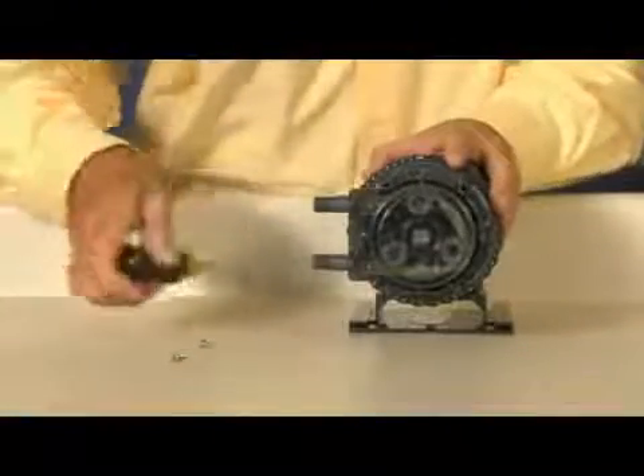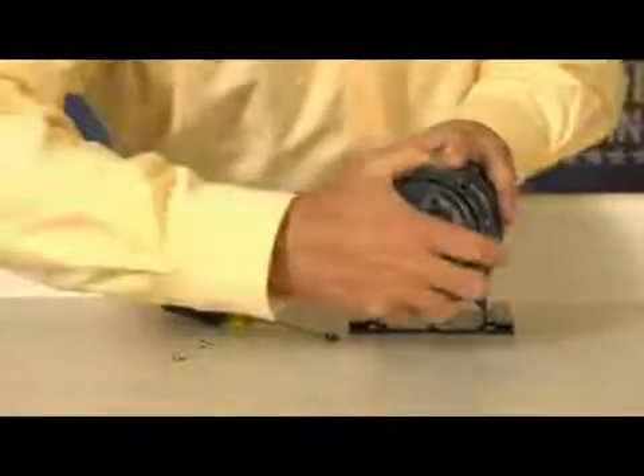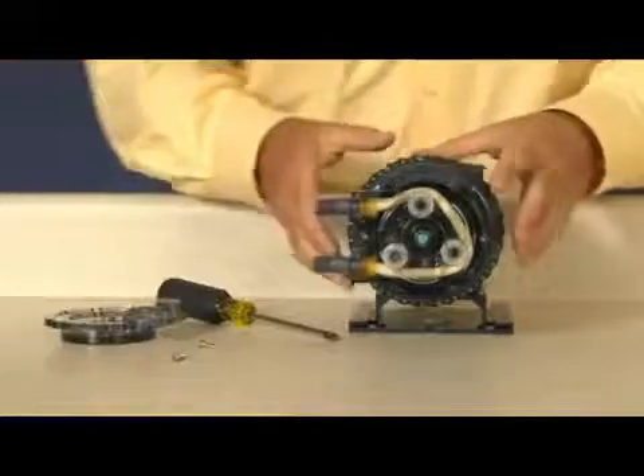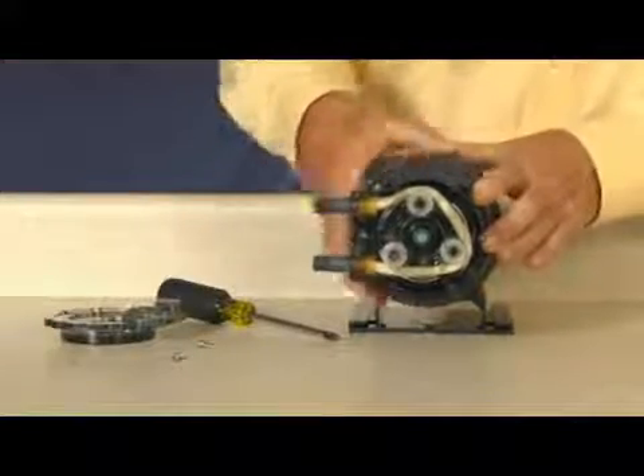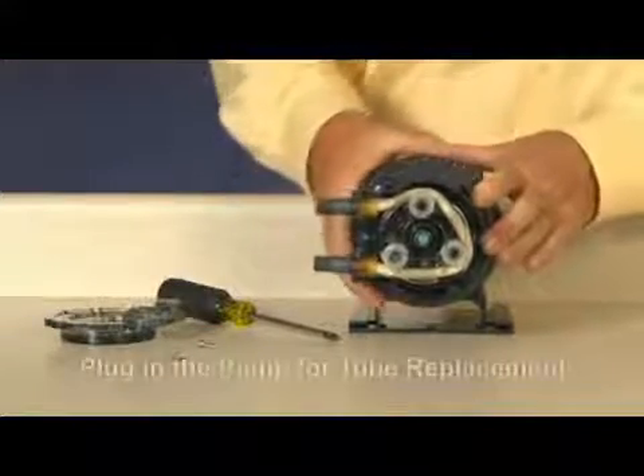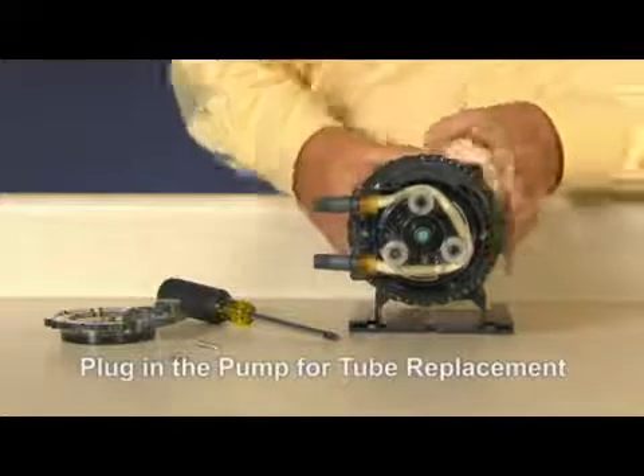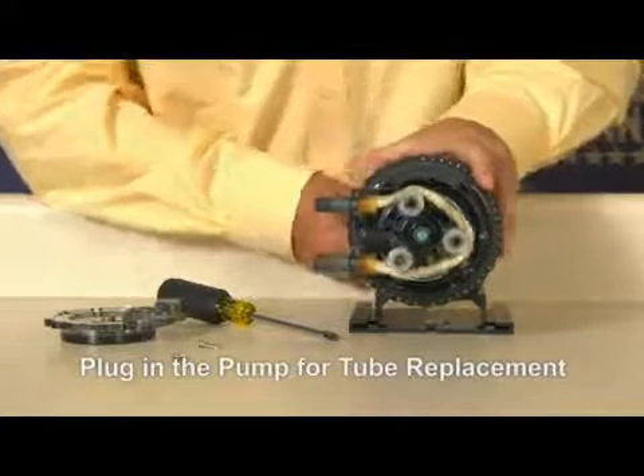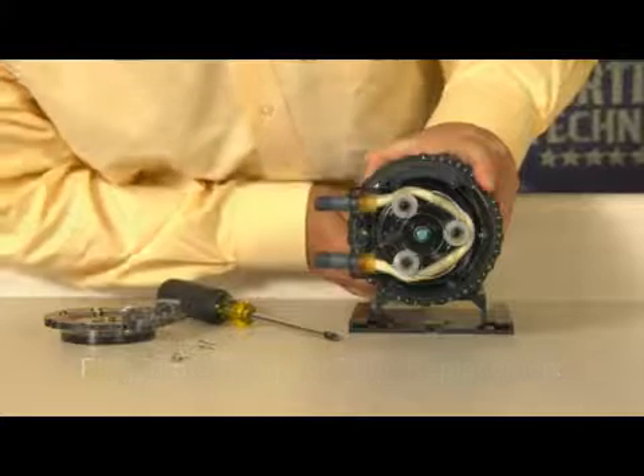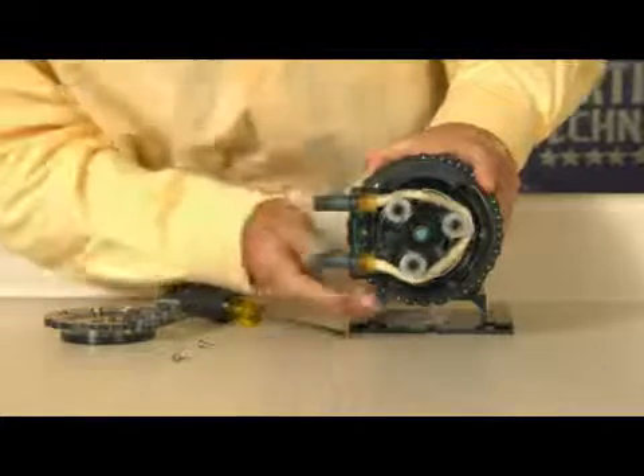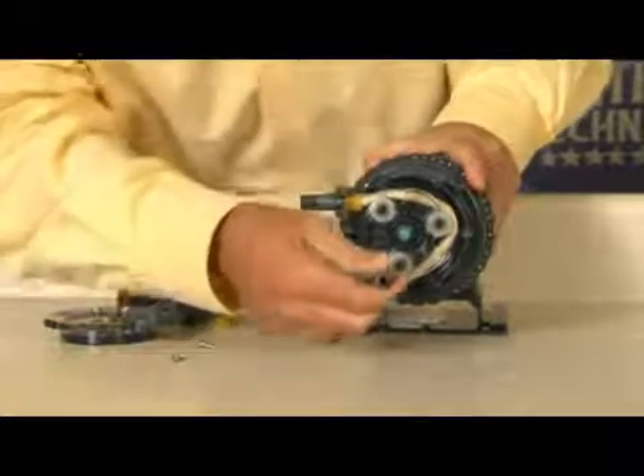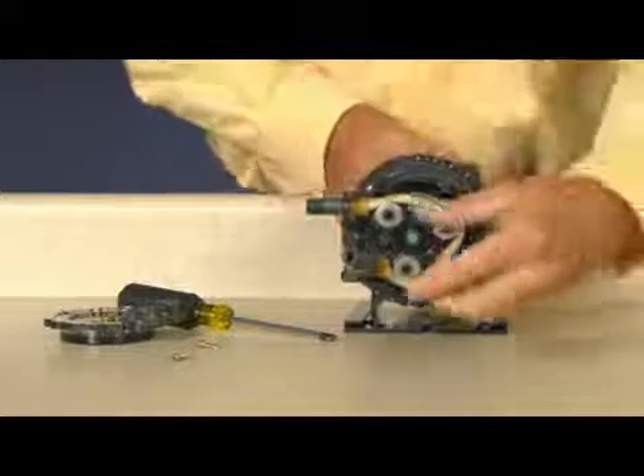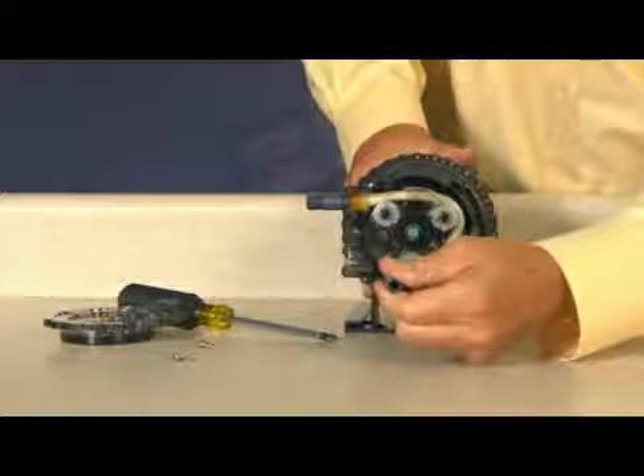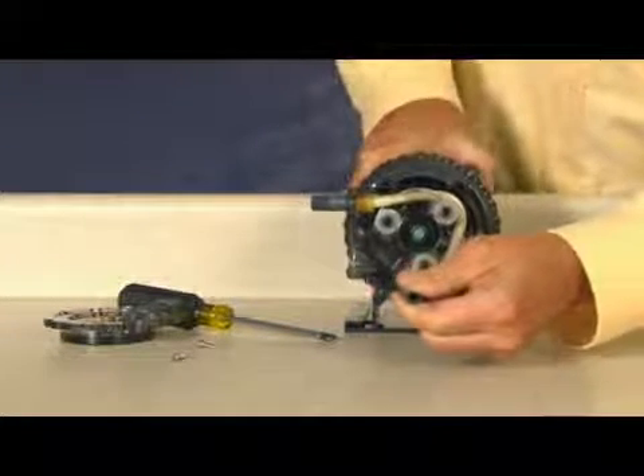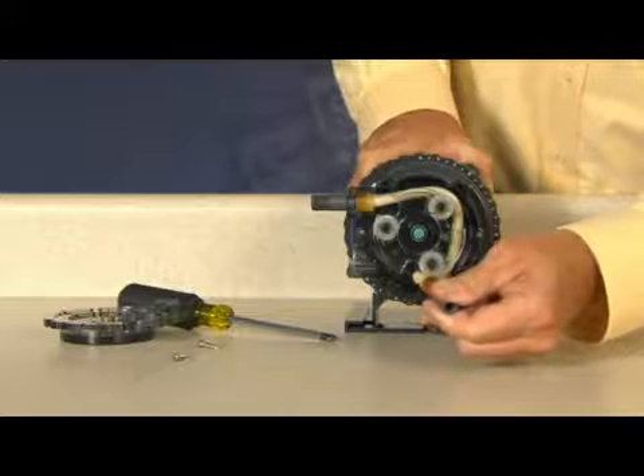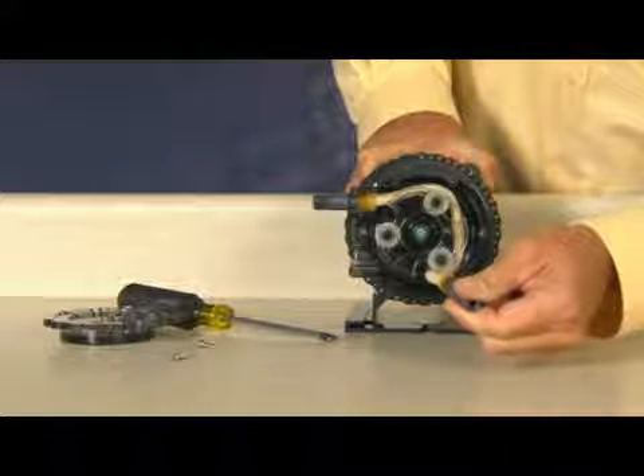To remove the pump tube, remove and set aside the pump head cover and screws. Set the feed rate control dial on setting L or 1. Turn the pump on and let it run until one of 3 roller assembly slots line up with the tube fitting on the suction side. Turn the pump off. Lift the tube fitting out of the housing slot and pull it toward the center of the roller assembly. Then, turn the pump on and allow the roller assembly to jog while guiding the tube with tension up and out of the housing.